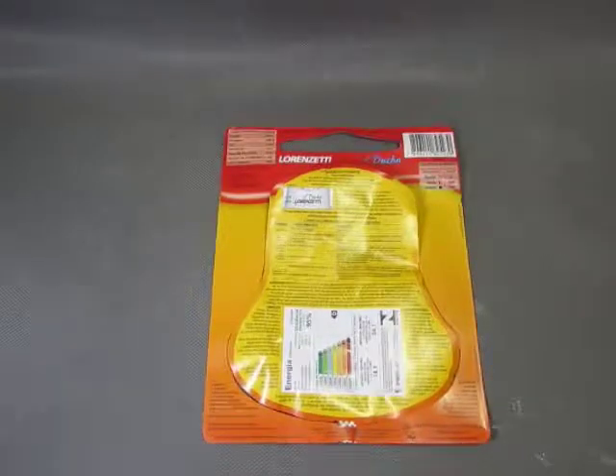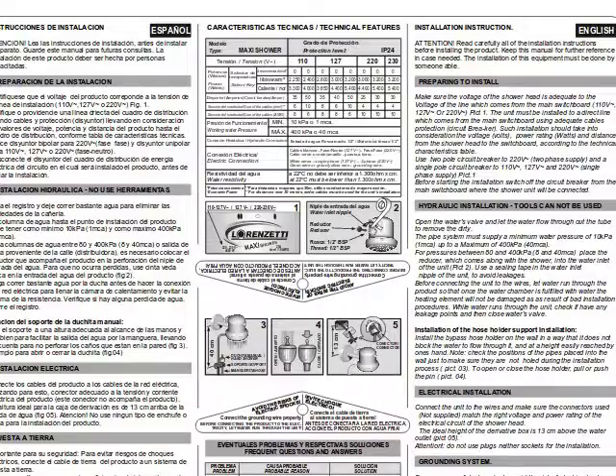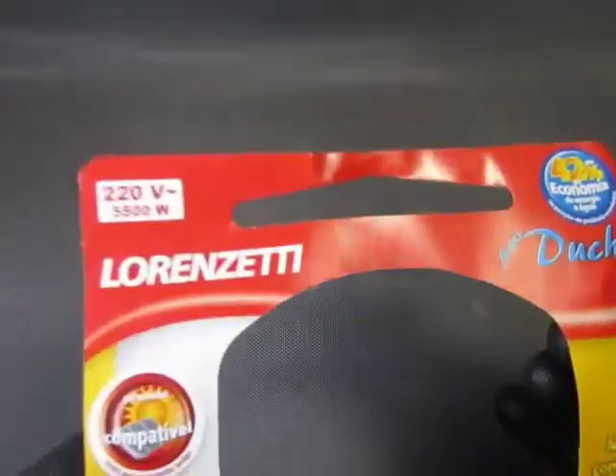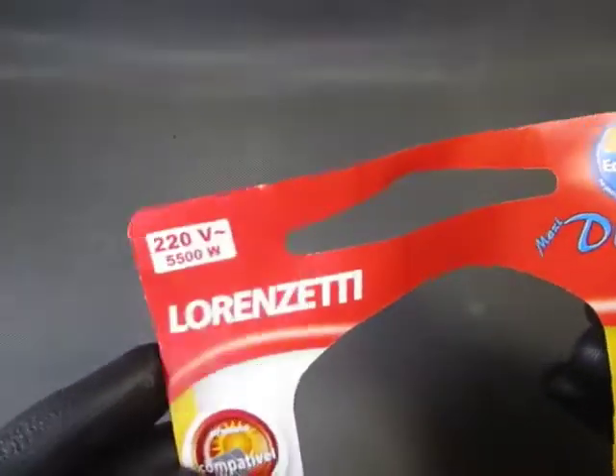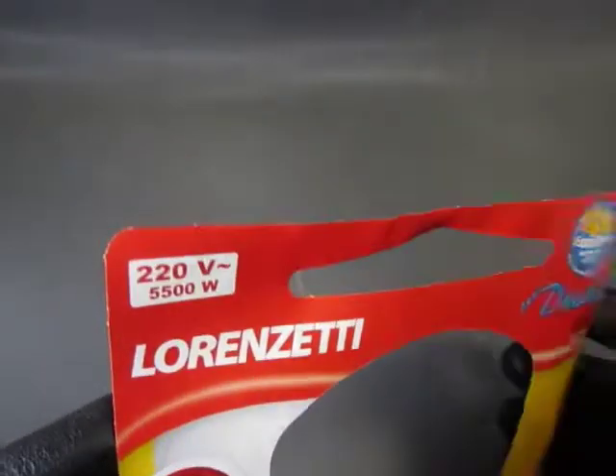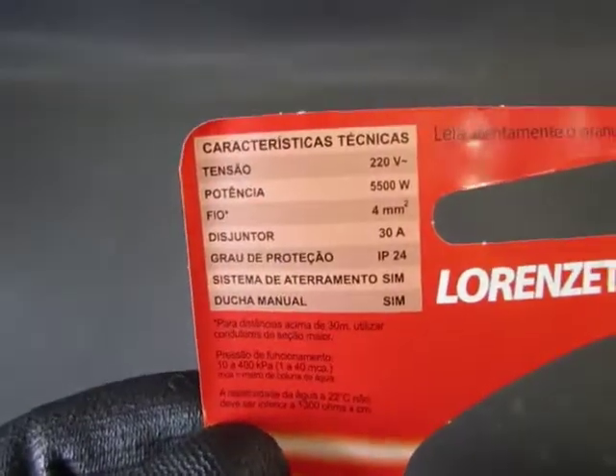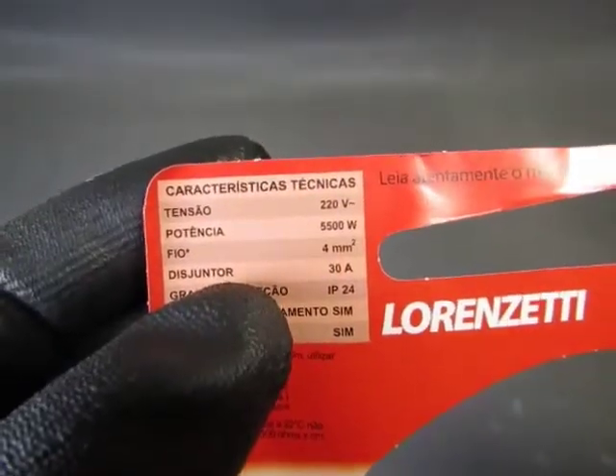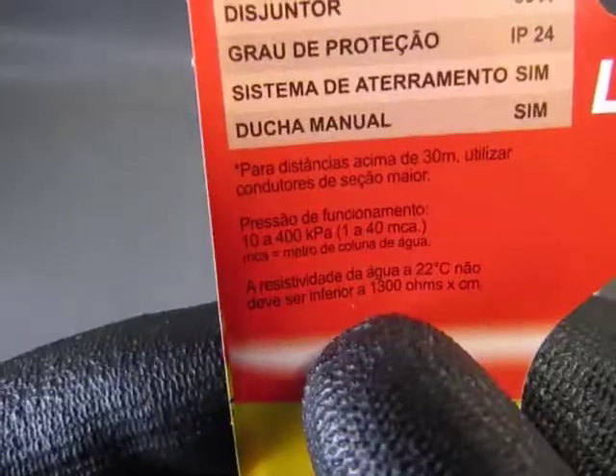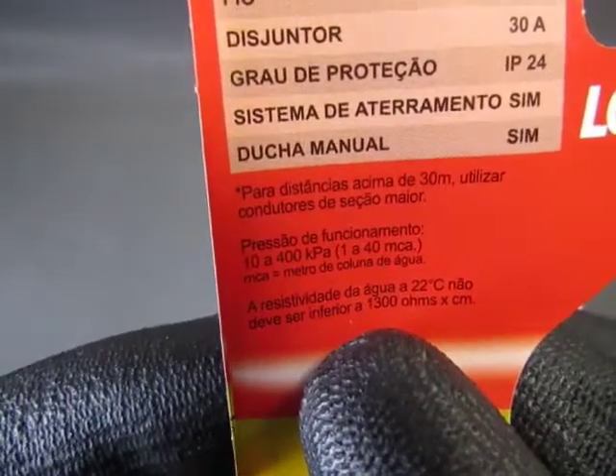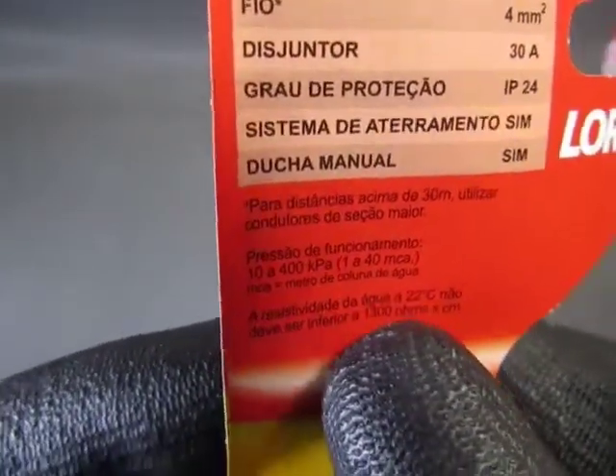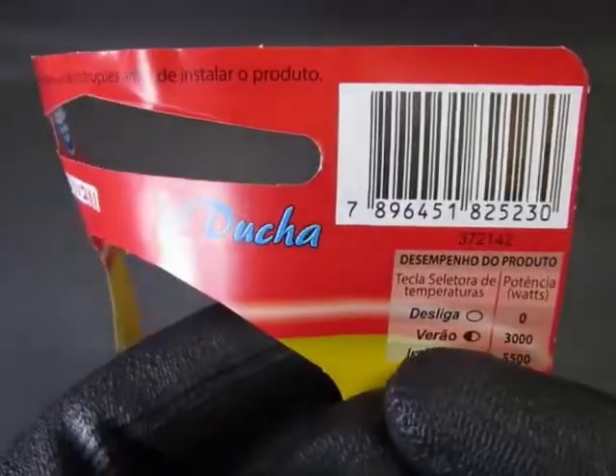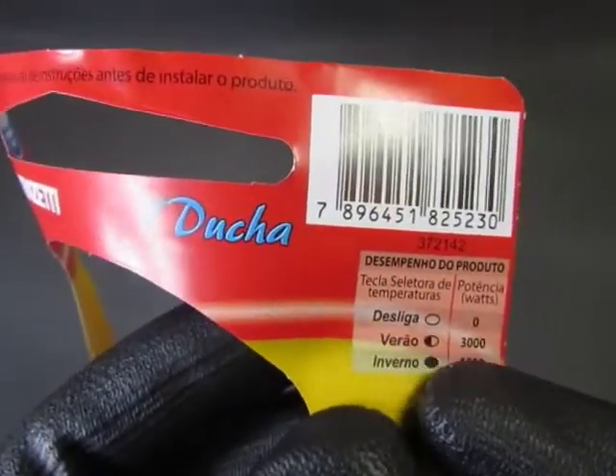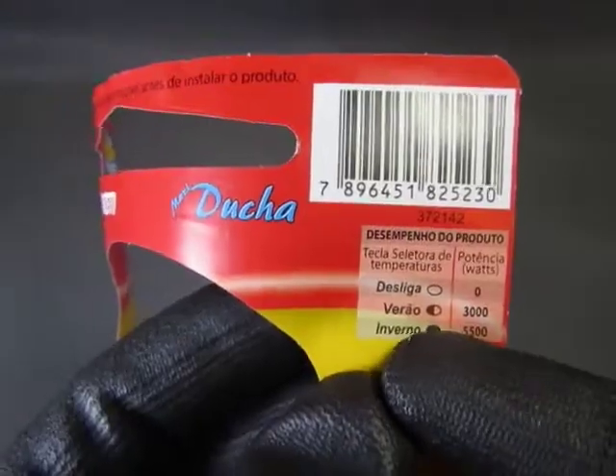It comes with a user manual. It is all in Portuguese, but you can find a somewhat abridged version in English and Spanish on their website. The voltage and power rating for this model are 220 volts, 5.5 kilowatts. On the back side we have more technical information. It rates the circuit breaker for 30 amps. It says that the water resistivity should not be inferior to 1.3 kilo ohms by centimeter. Here it shows that on the lower temperature setting it consumes only 3000 watts.